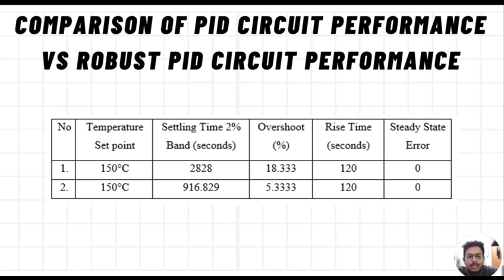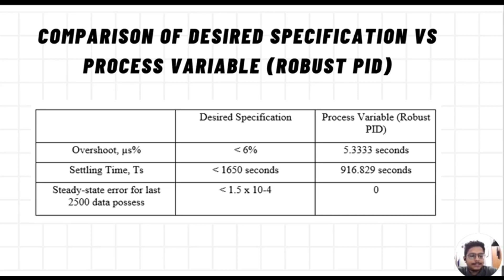Next is the comparison of design specification versus process variable for robust PID. The robust PID meets the overshoot requirement, which should be less than 6%, with an overshoot of 5.333%. It also meets the settling time requirement, which should be below 1650 seconds, with a settling time of 916.829 seconds. Additionally, it meets the steady state error requirement, which should be less than 1.5 times 10 to the power of -4, with a steady state error of 0. So from here we can say that the robust PID circuit successfully achieves the desired specifications, demonstrating lower overshoot, shorter settling time, and zero steady state error. And its additive and compensatory mechanism enhance control performance, accuracy, and robustness.